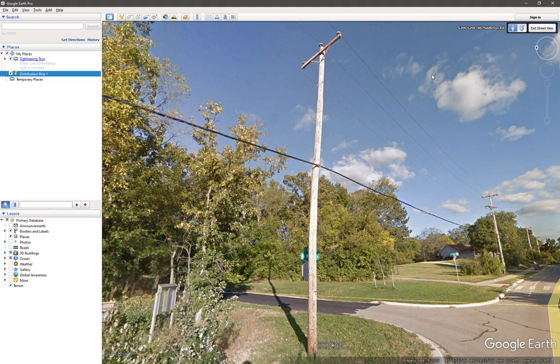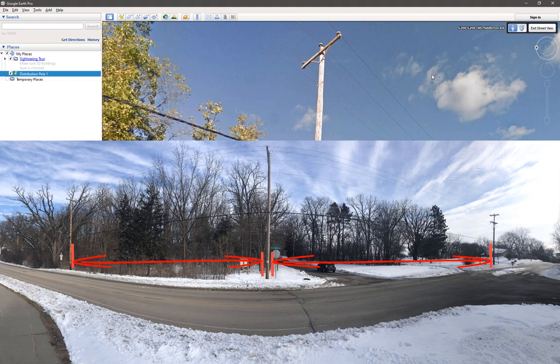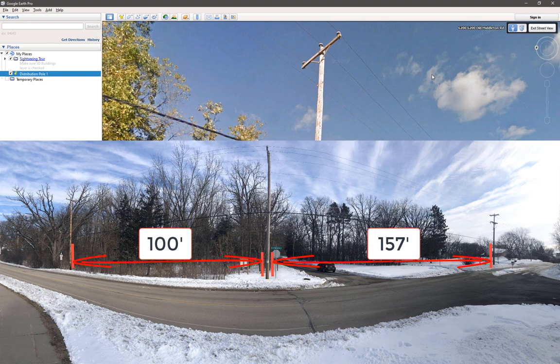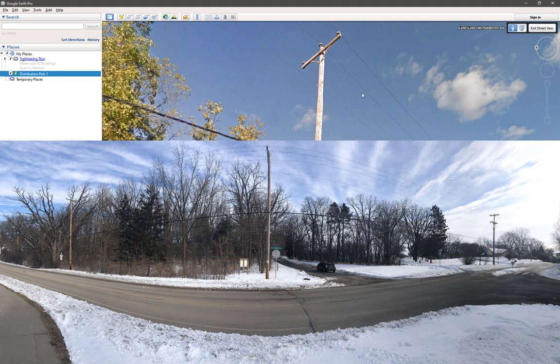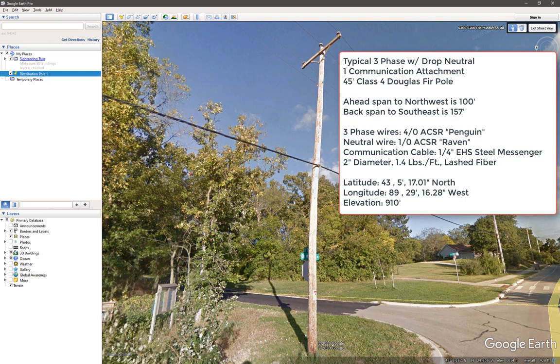We also took measurements in the field of the span lengths using a simple range finder and determined the span lengths to be about 100 feet to the northwest and 157 feet to the southeast. The terrain is fairly close to flat, and the adjacent poles were of the same height and framing, so we'll assume no vertical projection of the wire. We also determined that the three-phase conductor wires were 4-aught Penguin ACSR, and the neutral is a 1-aught Raven ACSR. The communication cable we discovered was a 1/4-inch EHS steel messenger cable, supporting a 2-inch diameter, 1.4 pound per foot communication cable.